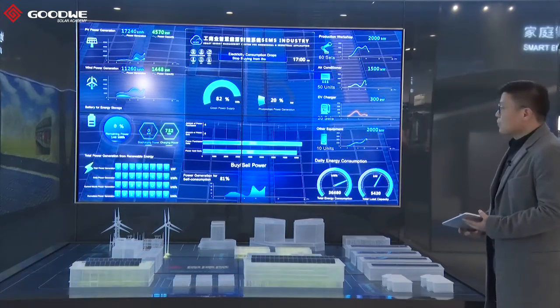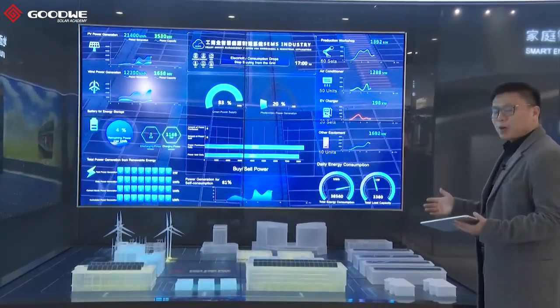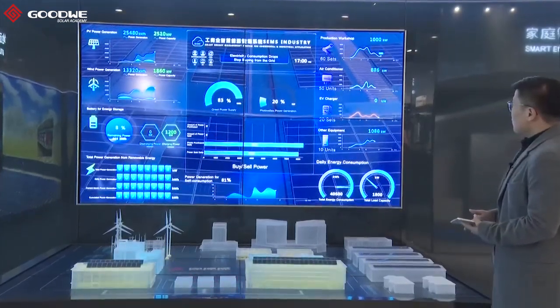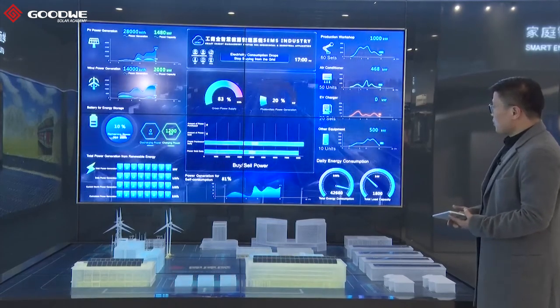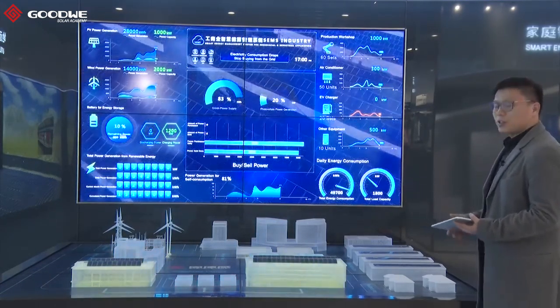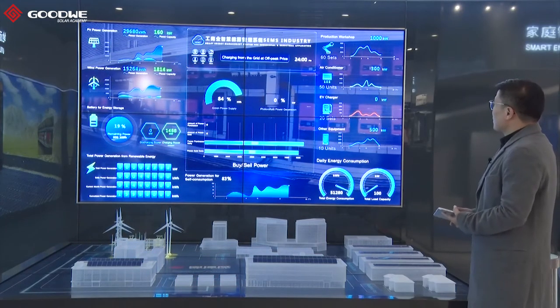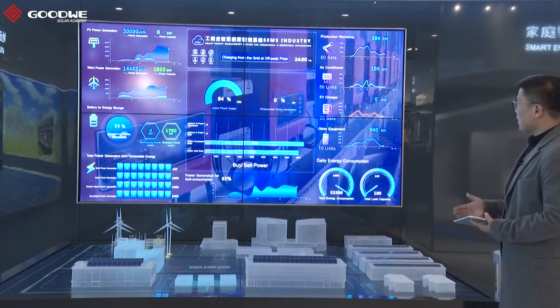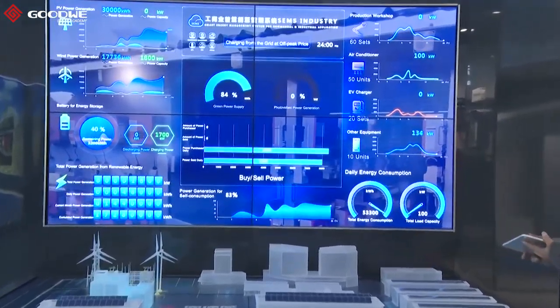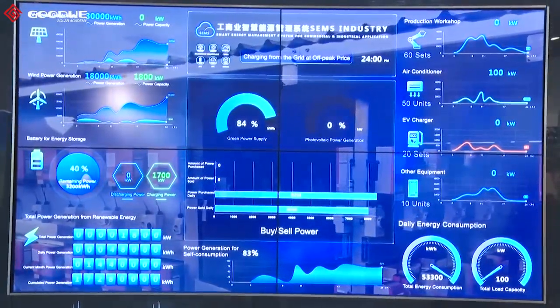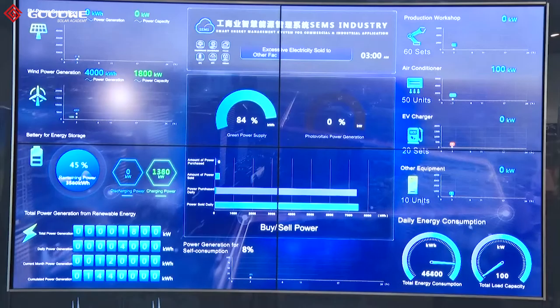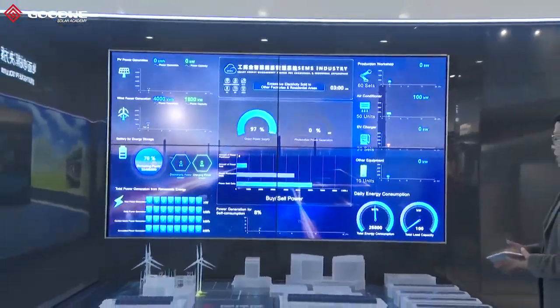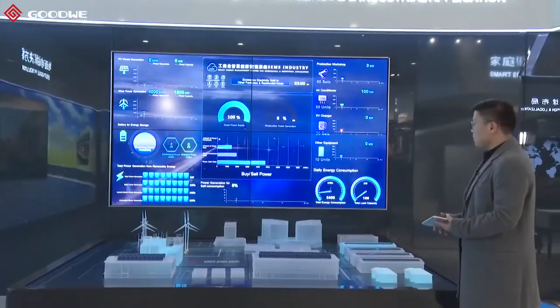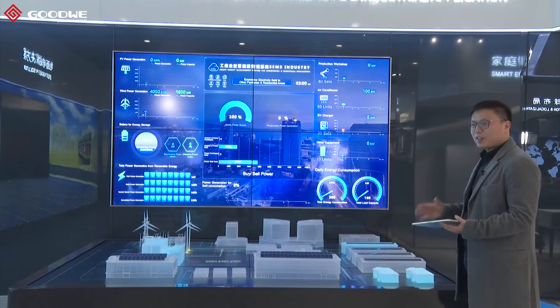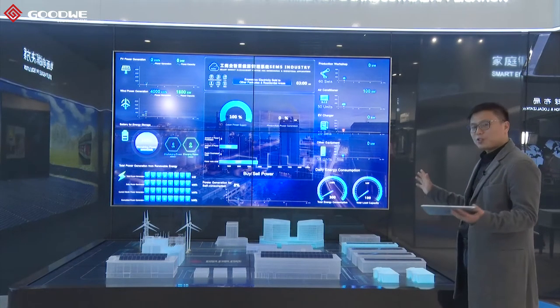Okay, now it comes to 5 p.m. The PV generation is less, and also the power load consumption is less. So you would stop buying electricity from the grid, and all the load consumption can be supplied by the storage system. So it's 12 a.m. in the night. You can charge the energy storage system from the grid because it's off-peak hours, right? So the electricity price will not be that much, and in that way, you can save your cost as well. Now 3 a.m. in the morning, you can allocate your power to supply other factories and some families as well. That's what we call the smart allocation of the power. So that's the whole concept of our industry energy management system.